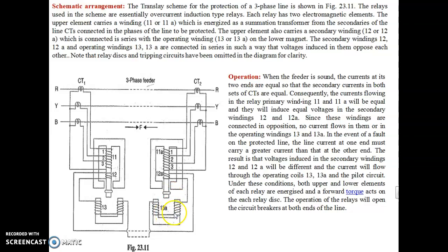See, the relay starts operating when a fault occurs in the middle, that is, in the middle of these two ends of the transformer, that is the transmission line. If an internal fault occurs at that time, what happens? The primary winding carries the current, and the secondary also carries the current. The secondary is directly connected to the lower magnet, that is the operating coil. The operating coil energizes, carries the current, and produces flux. So here one flux is produced, and the upper magnet also produces one flux, right? These two fluxes interact and produce the torque. Hence the flux that the operating coil produces gives an operating torque greater than the restraining torque produced at the lower side. If the operating torque is greater than the restraining torque, obviously our relay starts operating. Hence the relay operates, detects the signal, and sends the signal to the circuit breaker to trip the circuit.